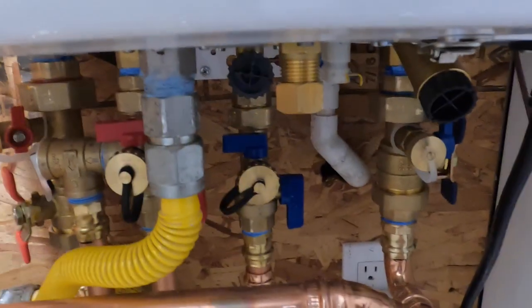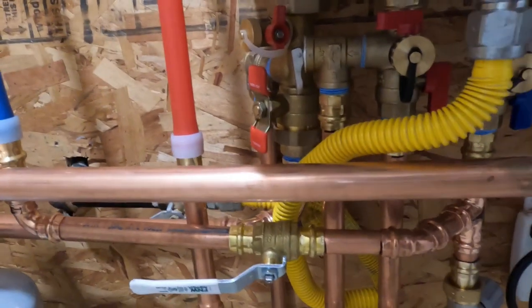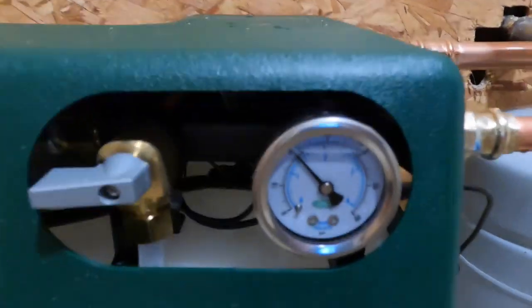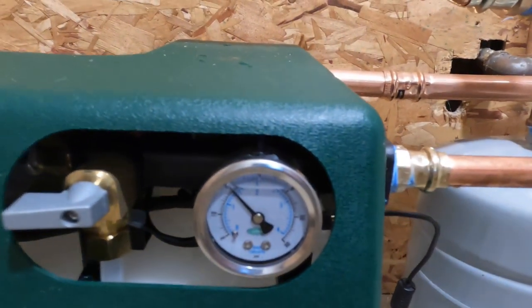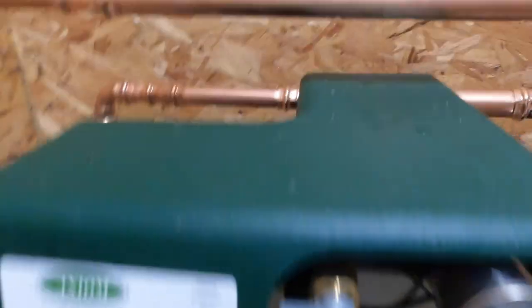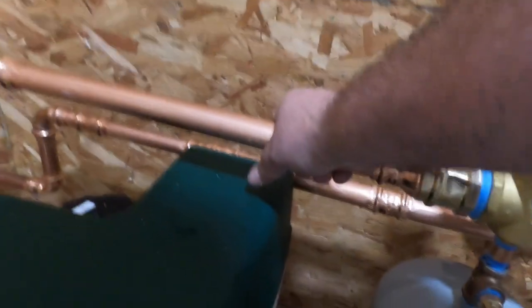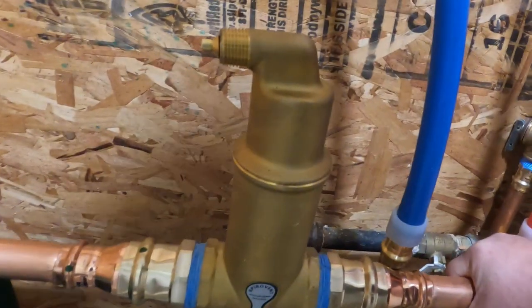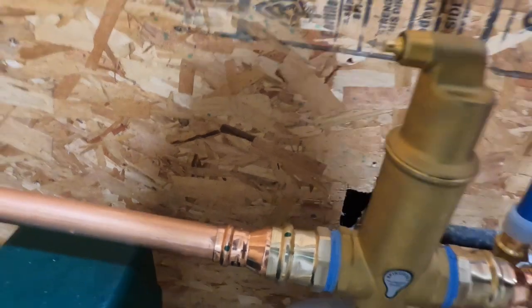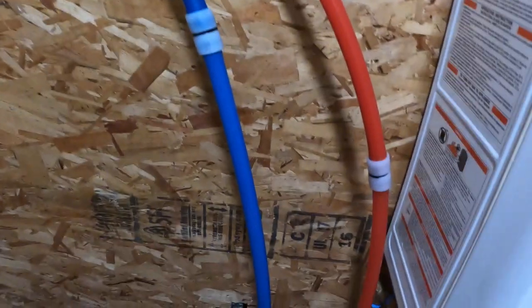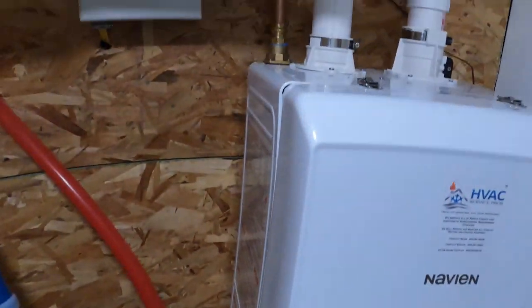All caps are in place. All flush valves are closed. All primary valves are open. Pressure gauge on the system is reading pressure. Floor loop is heating up. We're starting to get some warm water coming back. And we are good.